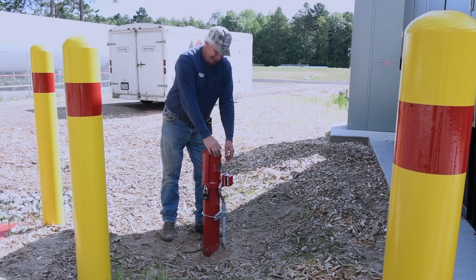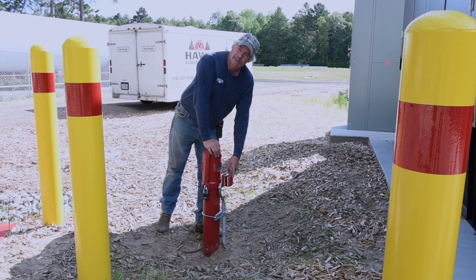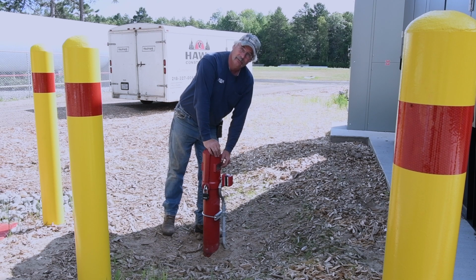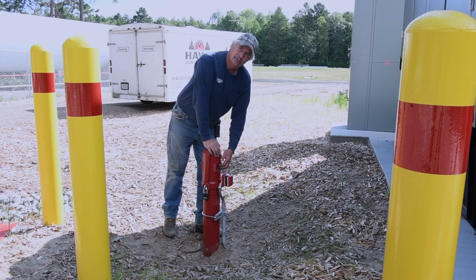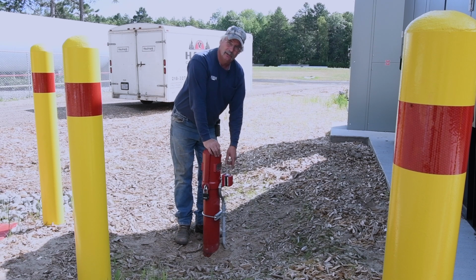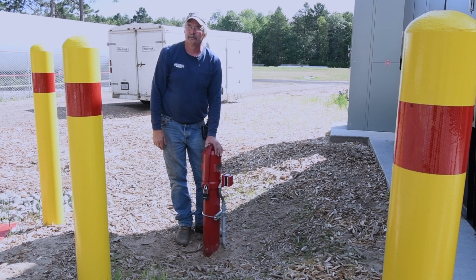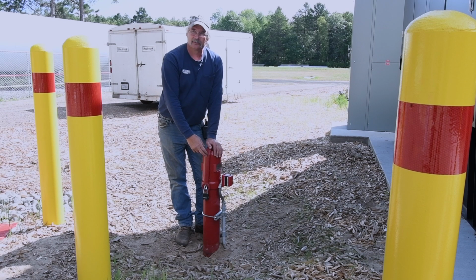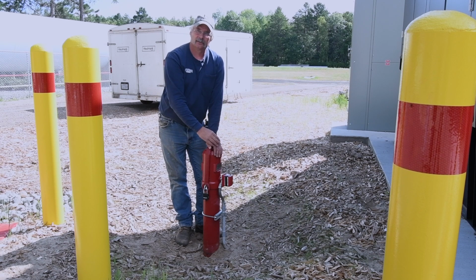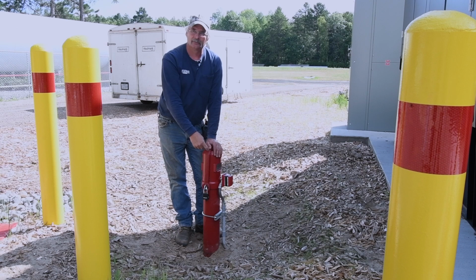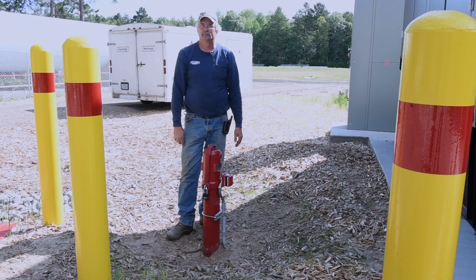Again, you have to identify this, get a hold of Ben Bowstring before you do any work on any of the sprinkler systems, because this is a tamper valve. If anybody shuts this valve, this tamper switch will go into alarm back to their panel immediately. And each one of these valves are identified in that panel, so it's going to tell you exactly that they shut this one off. How many valves are there and where are the locations?